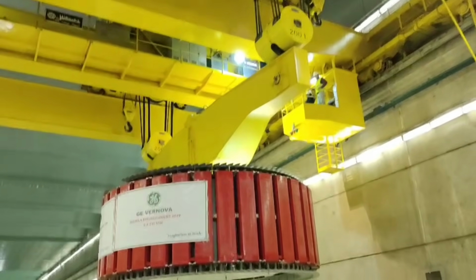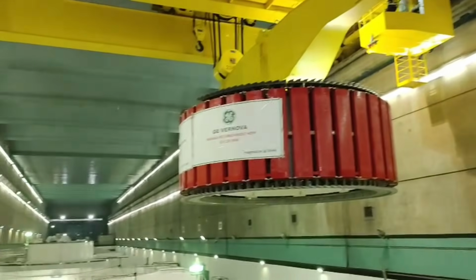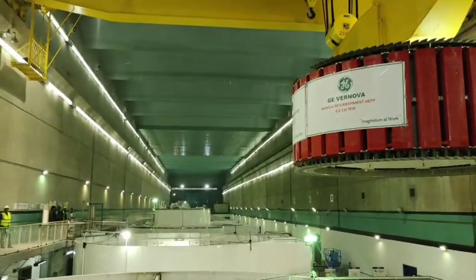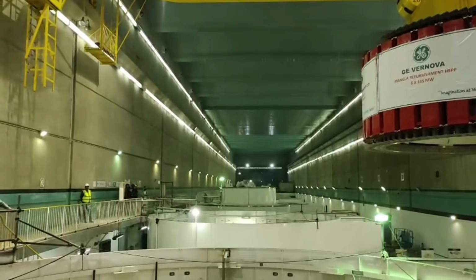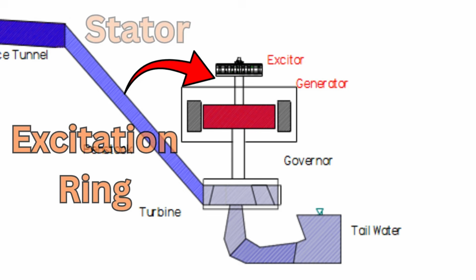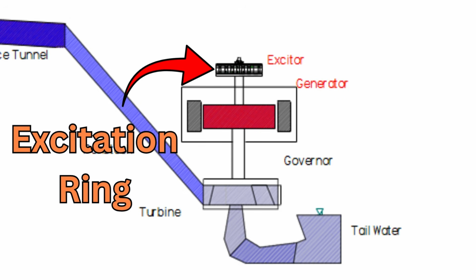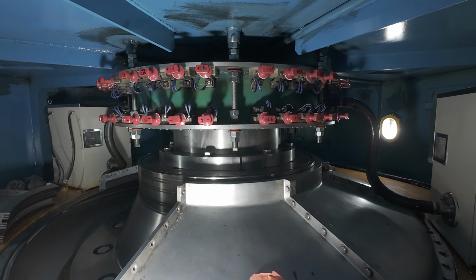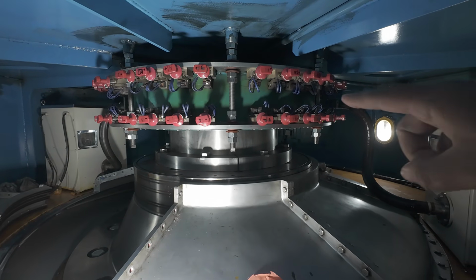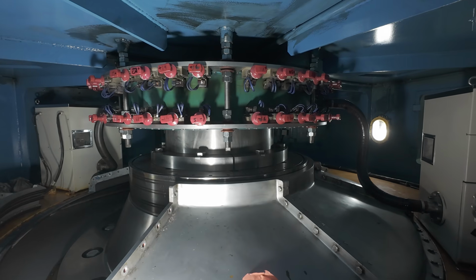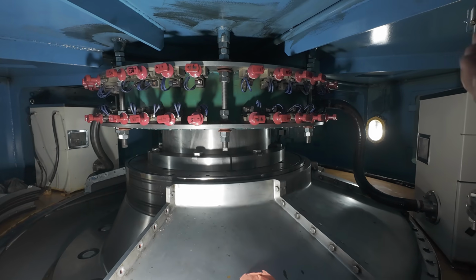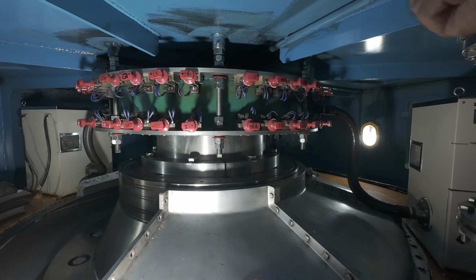So that's the job of the excitation system. But now another problem appears. How do you send electricity into a rotor spinning at full speed? So this is where the exciter rings and carbon brushes come in. Mounted on the shaft at the top are smooth metallic rings called slip rings, or the exciter rings. These rings rotate together with the rotor. Pressing against them are stationary carbon brushes.